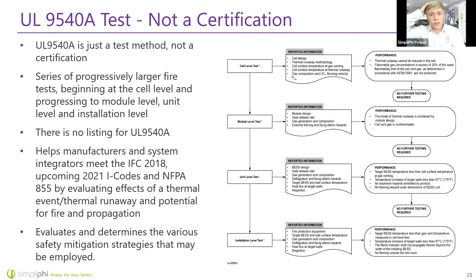Now we see 9540A. This is new, up and coming. It is not a certification, it is a test method. It's going to seriously light batteries on fire, see how they react to being pushed and forced into thermal runaway, and evaluate the safety features at mitigating thermal runaway, and also see what occurs when those safety features are bypassed.